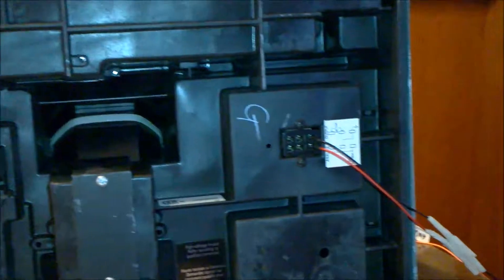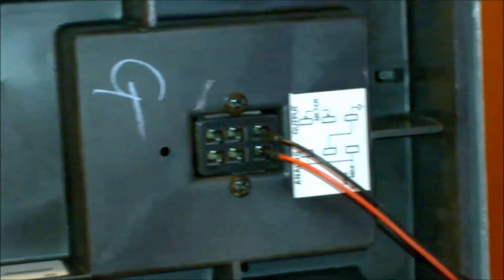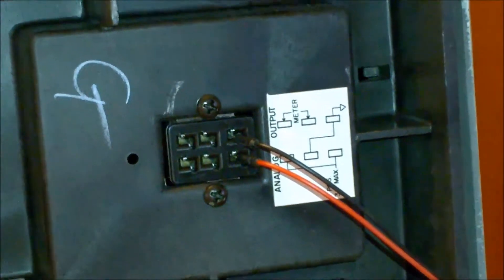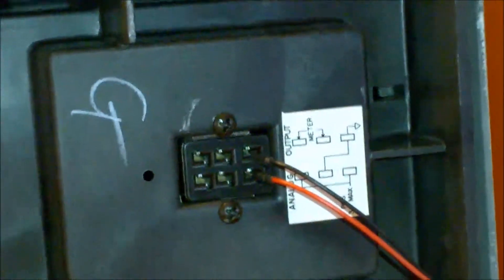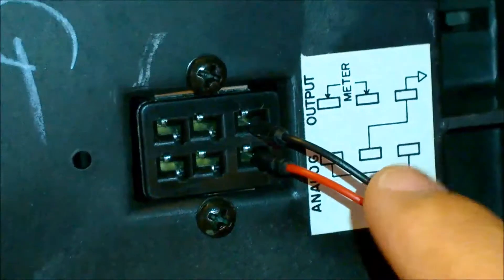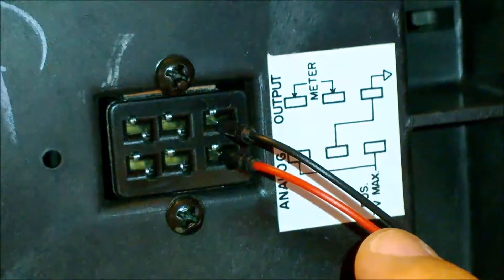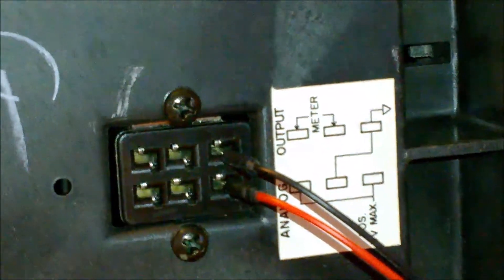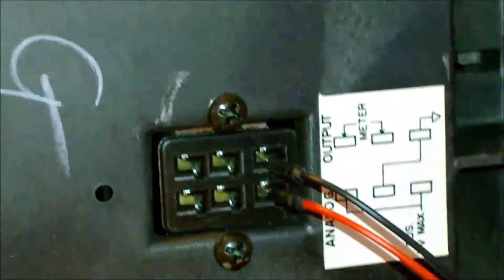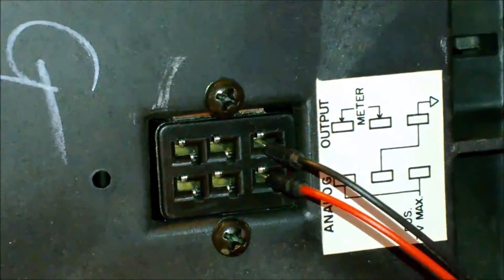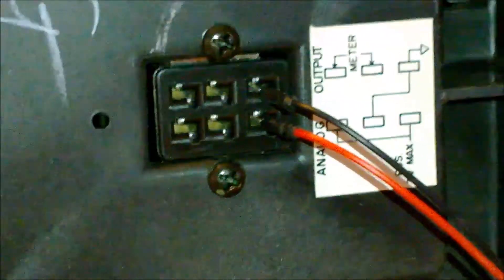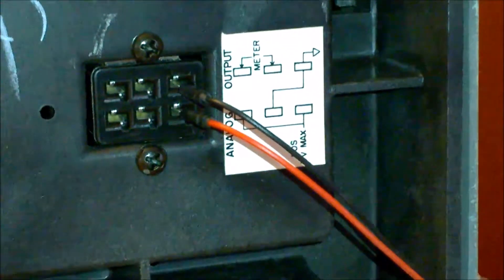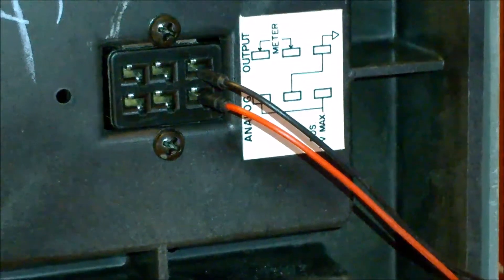If you look under the Spectronic 20 spectrophotometer, you can see that there are some analog outputs. These are the two pins which are connected here - this is the ground and this is the analog output. Corresponding to zero to 100 percent transmittance, voltage on this output will go from zero volt to one volt. So now it will be a simple matter of reading these voltages and displaying on a Processing software.